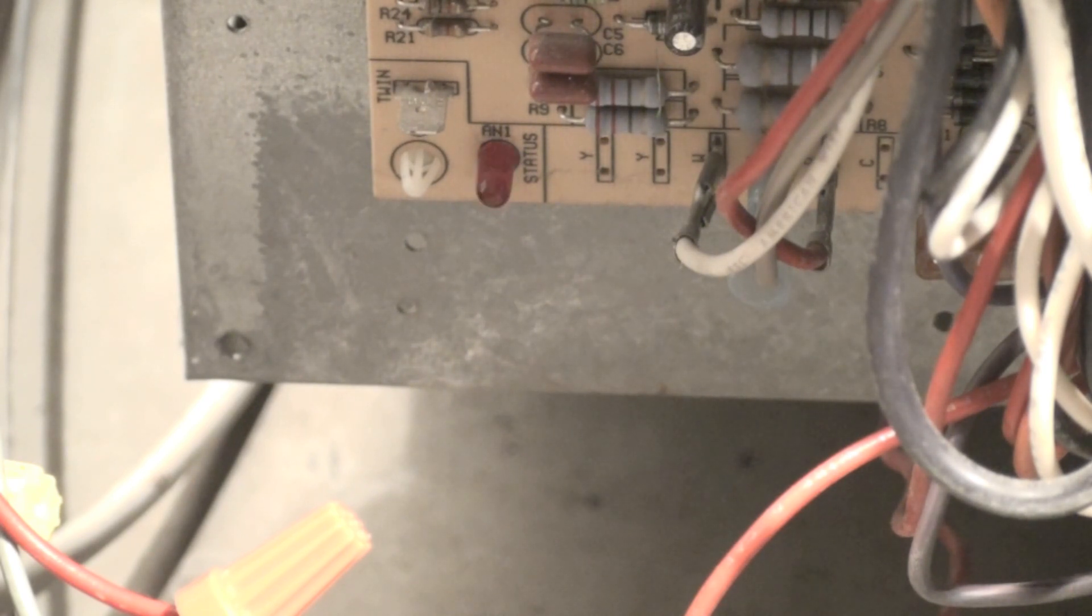Okay, so you know the limit switch safety is out as it should safety out. If it did not safety out and just kept heating after this thing goes for four or five minutes, I'd better get this thing turned off because it's going to cook the heat exchanger.